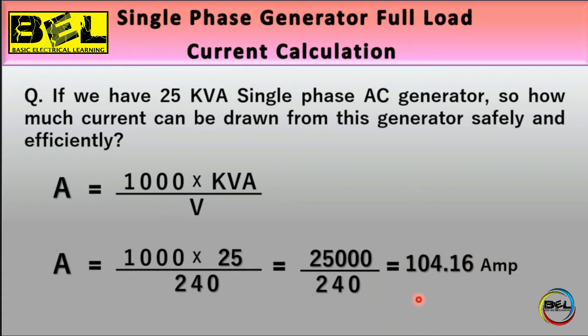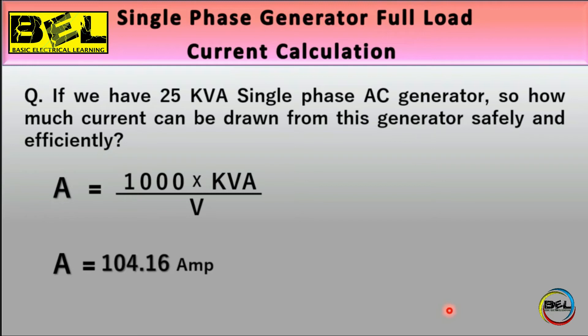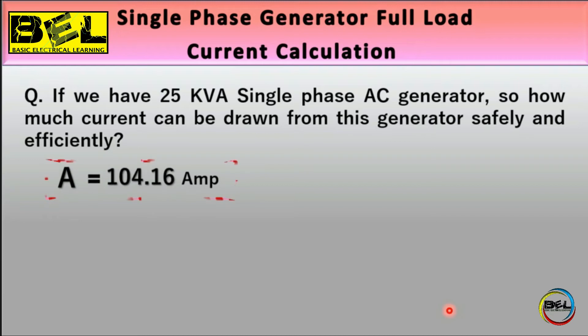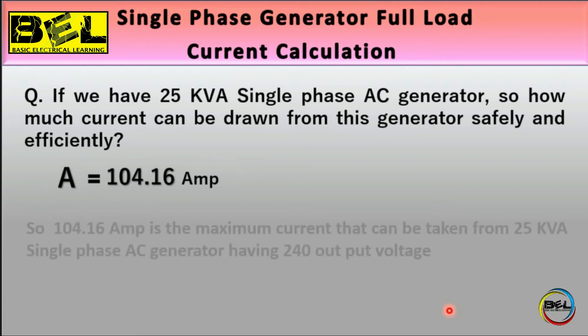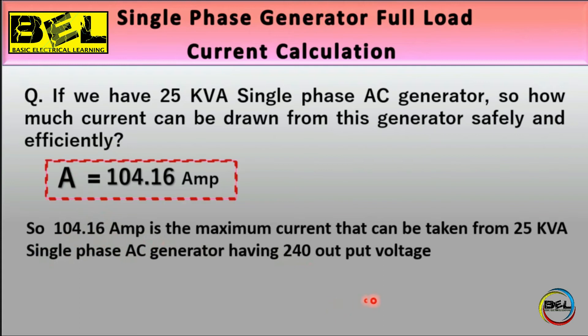So 104.16 amperes — approximately 105 amperes — is the maximum current that can be drawn from a 25 kVA single phase AC generator at 240 V AC. However, the maximum current should never be drawn continuously for safe operation.